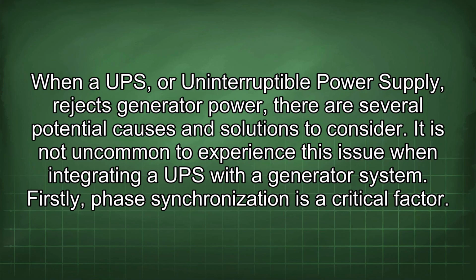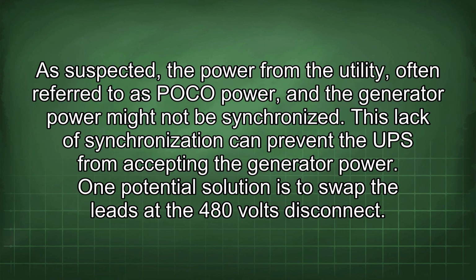When a UPS, or uninterruptible power supply, rejects generator power, there are several potential causes and solutions to consider. It is not uncommon to experience this issue when integrating a UPS with a generator system. Firstly, phase synchronization is a critical factor. As suspected, the power from the utility, often referred to as POCO power, and the generator power might not be synchronized. This lack of synchronization can prevent the UPS from accepting the generator power.